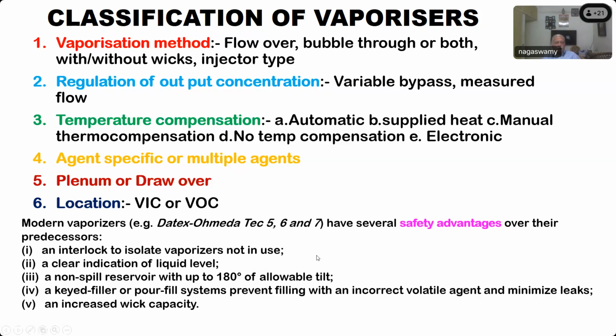So how will it be indicated? What position do you have to keep the dial in if you don't want any spillover from the vaporizing chamber reservoir to come into the breathing circuit? In the dial, you will have a particular alphabet there. T, sir. T for tilt. It is here. So allowable tilt. Okay. So if you keep the dial fixed in the T position, that means you cannot spill the liquid from the vaporizing chamber into the common area.